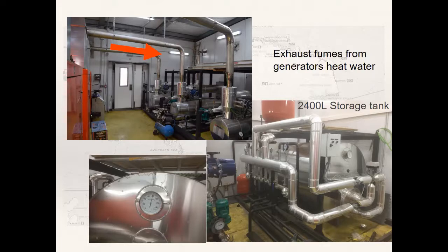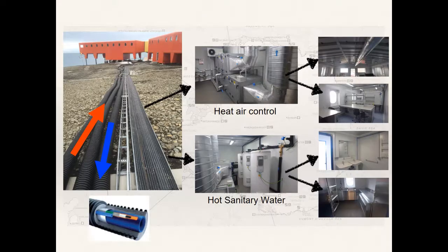The system is made up of 3 400-liter aluminum tanks connected to the exhaust of each generator where water is heated. Hot water is stored in a 2,400-liter tank at 80 Celsius degrees and pumped out to the different modules. As Juan Carlos I station is constructed in several modules, specially insulated pipes were used to reduce the heat losses in the transfer of hot water to the different modules.